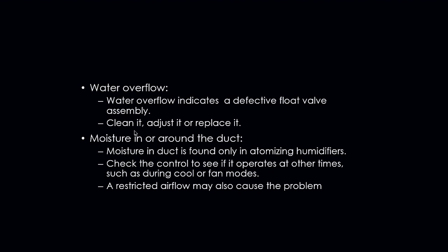Okay? Moisture in or around the duct. Moisture in the duct is found only in atomizing humidifiers. Check the control to see if it operates at other times, such as during the cooling mode or if the fan on mode is on. Okay, sometimes it could simply be miswired. Okay, restricted airflow may also be causing a problem. Do they have the dampers in the ductwork closed? So you might want to look at that.